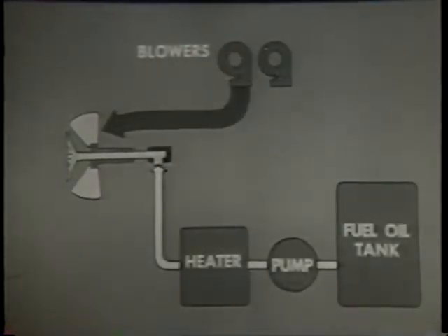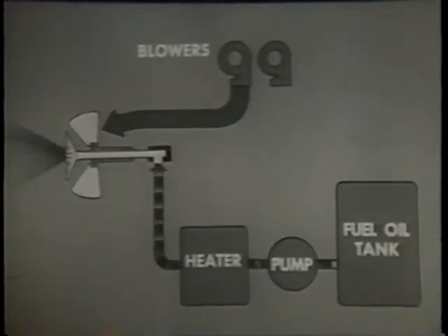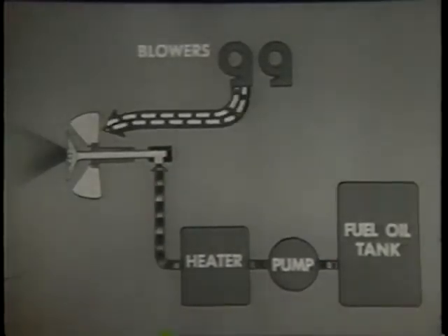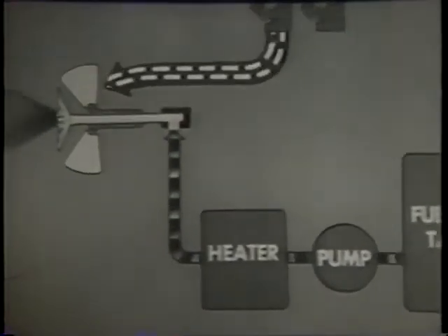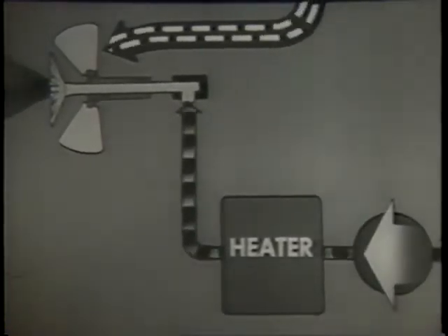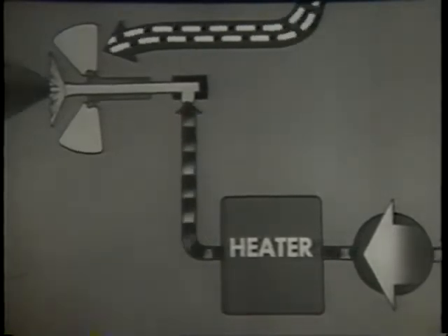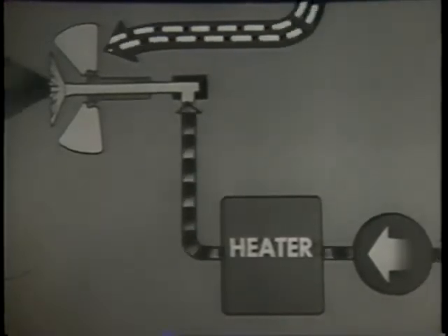You control the firing rate of the burner by varying the amount of fuel oil flowing through the burner. Of course, you must make corresponding changes in the amount of air reaching the burner when you change the amount of fuel oil. When you increase the pump pressure on the fuel oil line, you increase the quantity of oil going through the burner. When you decrease the pressure, you decrease the quantity of oil. However, when you want an increase in the firing rate, the sprayer plate in use at the time may have too small a capacity — that is, too small an opening to provide the necessary quantity of oil, even with oil pressure at maximum. You must substitute a plate with a larger capacity.